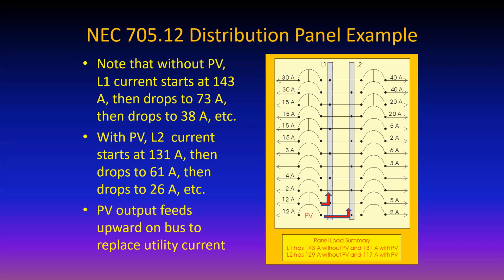So there's a calculation you make that says that the sum of the PV breaker plus the main breaker has to be less than 120% of the rating of the bus bar. And that almost always happens.